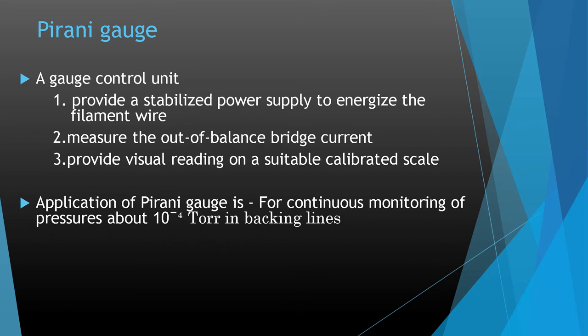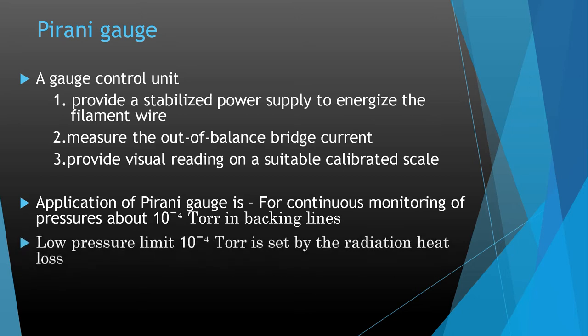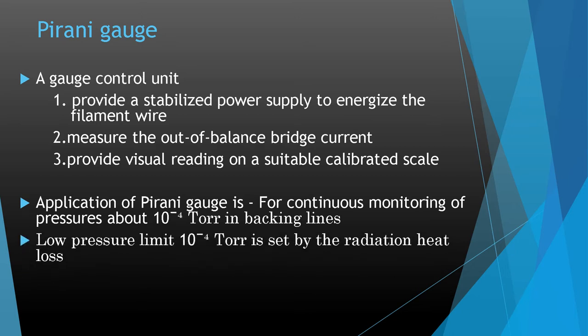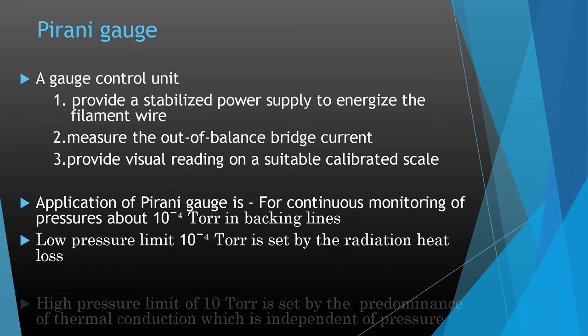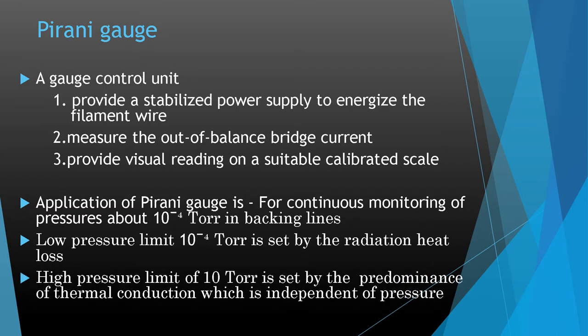The application of the Pirani gauge is for continuous monitoring of pressures around 10⁻⁴ Torr in backing lines. The low pressure limit of 10⁻⁴ Torr is set by the radiation heat loss, and the high pressure limit of 10 Torr is set by the predominance of thermal conduction which becomes independent of pressure. This concludes the Pirani gauge.